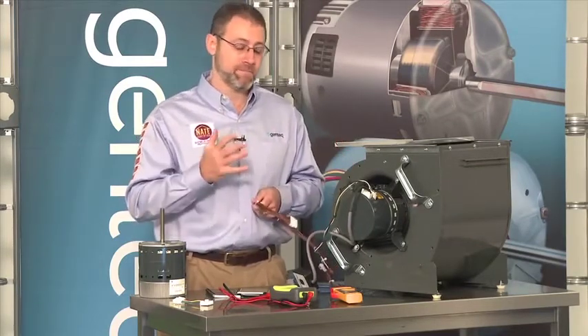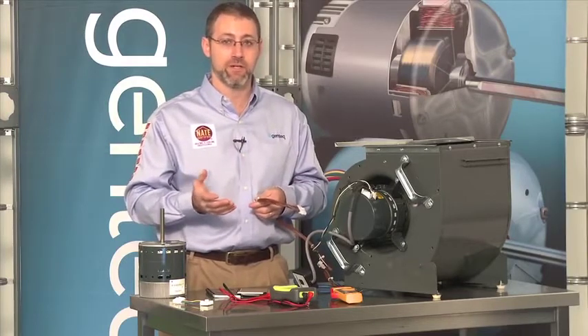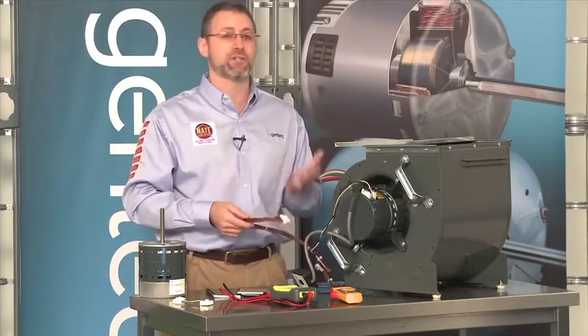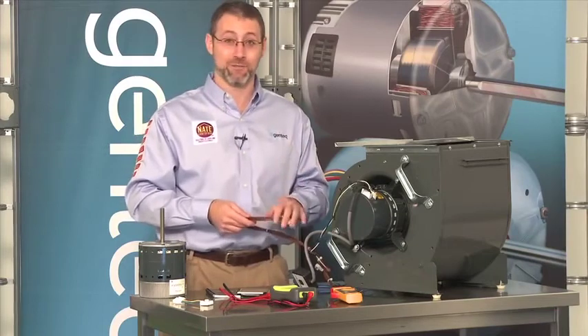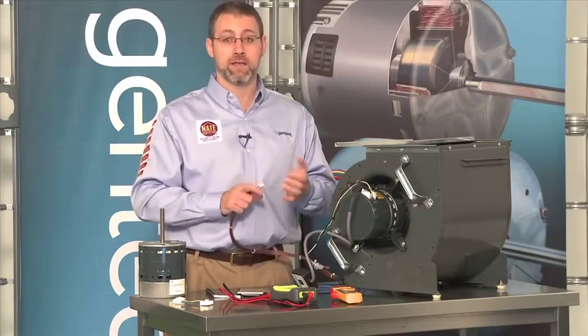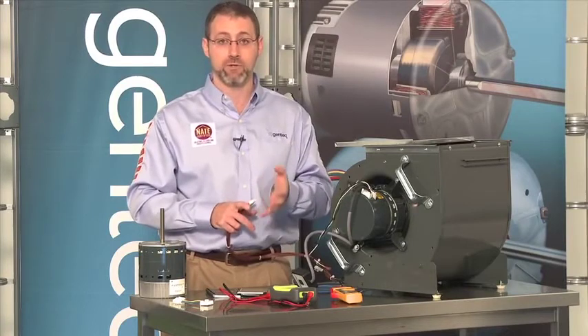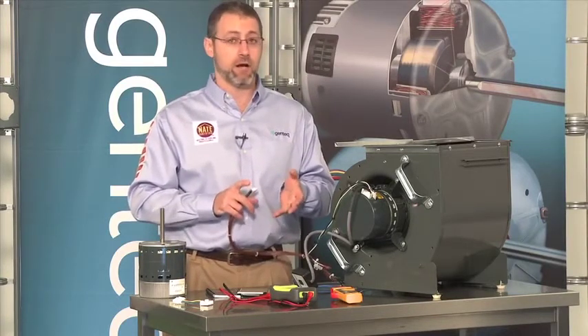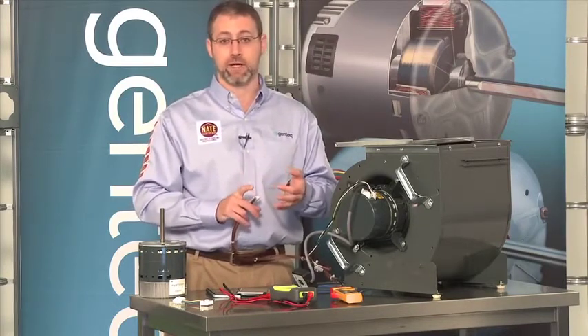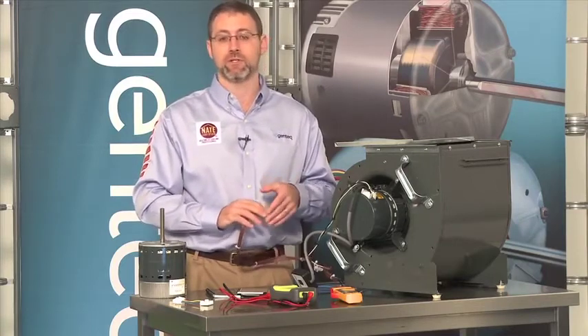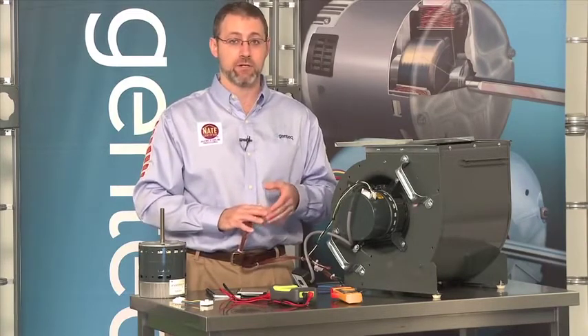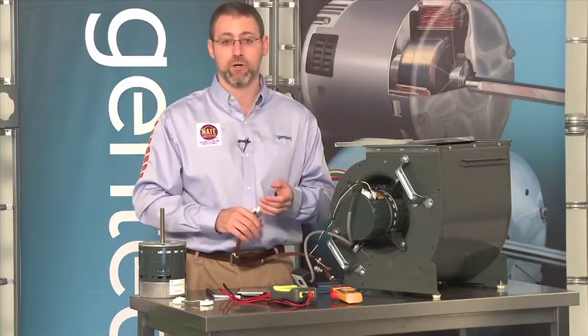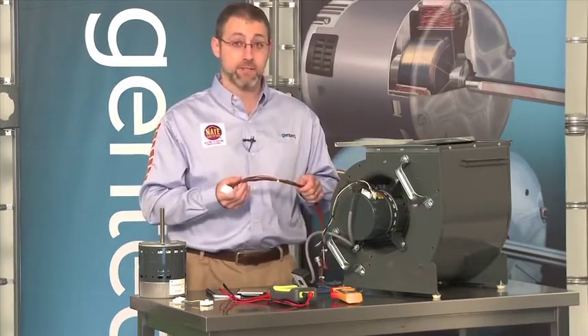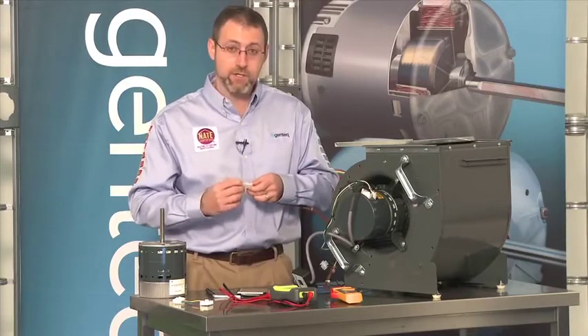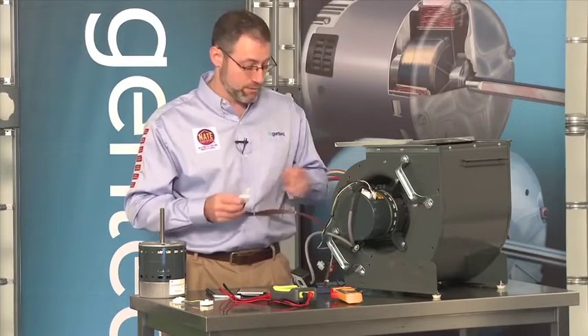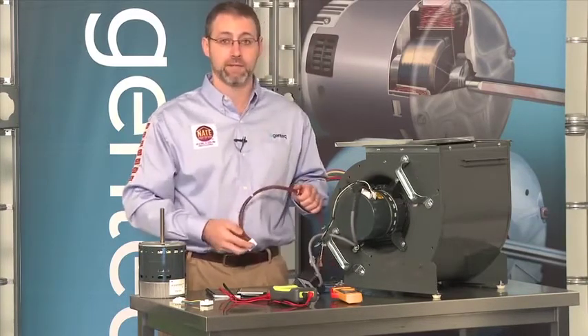And I was in the field for about 10, 15 years, and I remember what it was like to want to say, oh, it's just the board. Well, it's not always just the board. We have to remember that the thermostat demand has to be coming down to the board to tell it when to turn on. Our low voltage wiring needs to be connected correctly. We could have tripped safety switches. Is the sequence of operation at a time frame where the motor should turn on? Is the 16-pin connector in good shape? There's a lot of very small pins in this harness, and we would want to check them from the motor all the way back to the board.